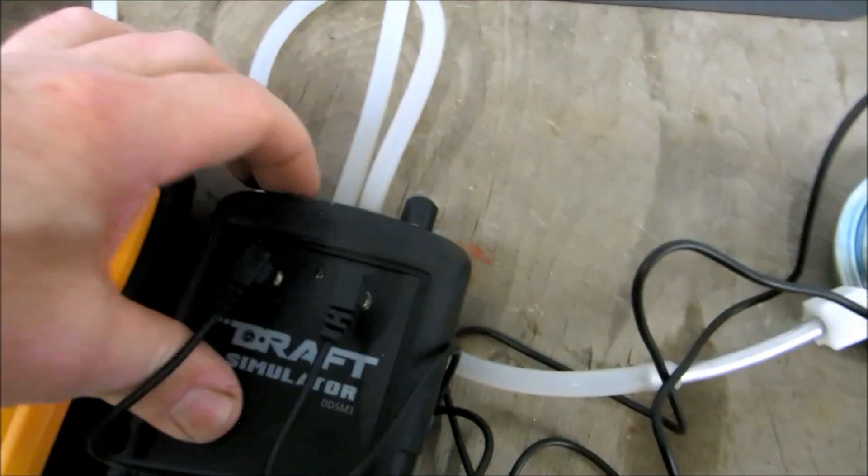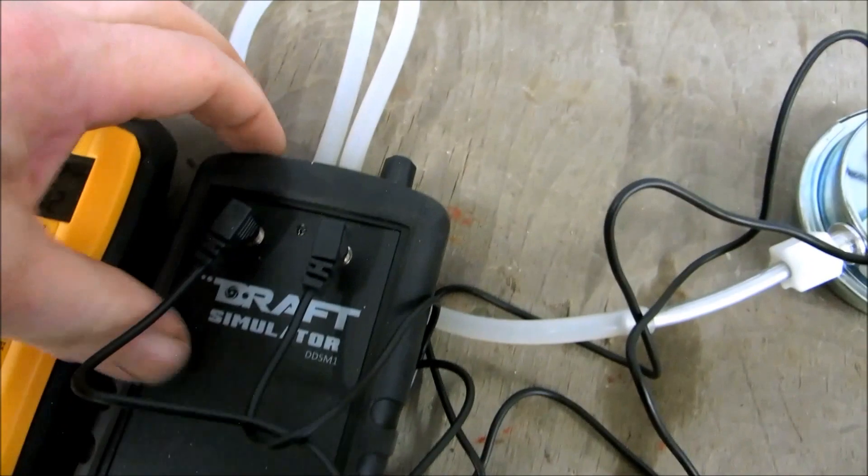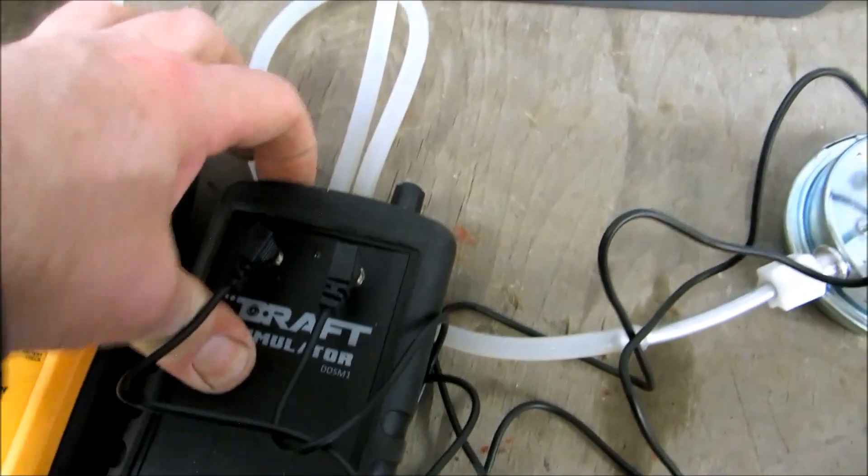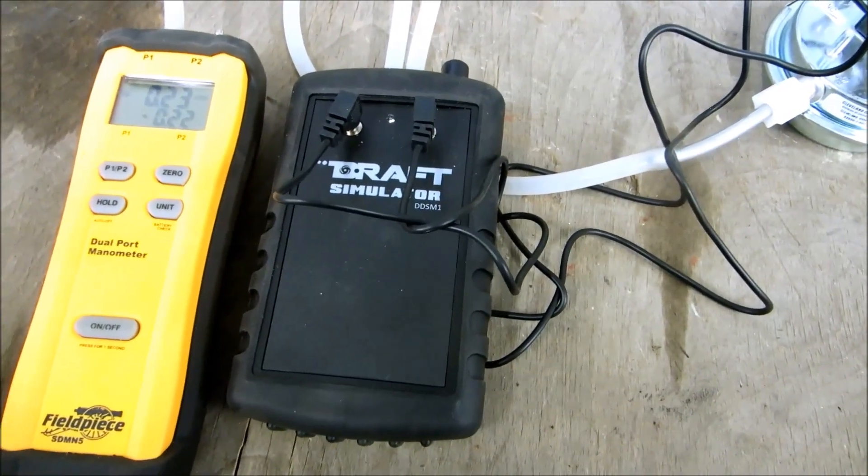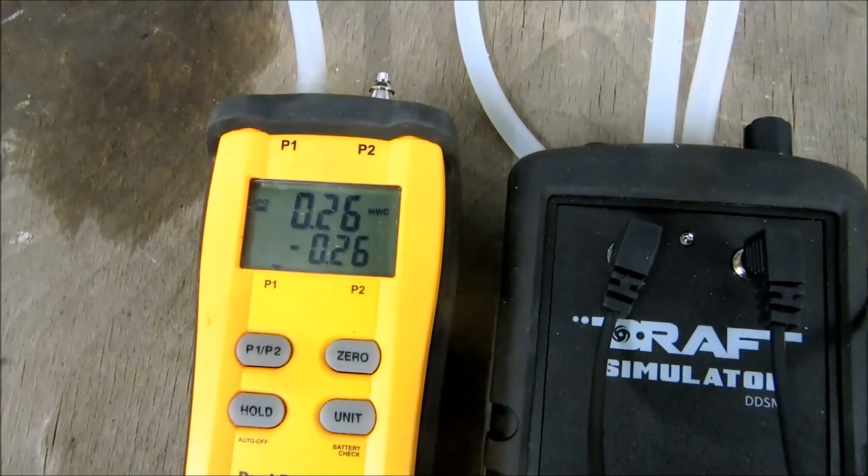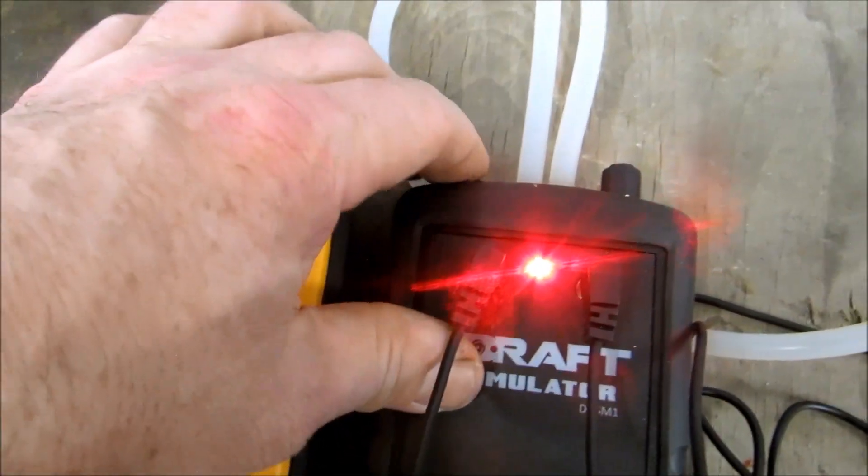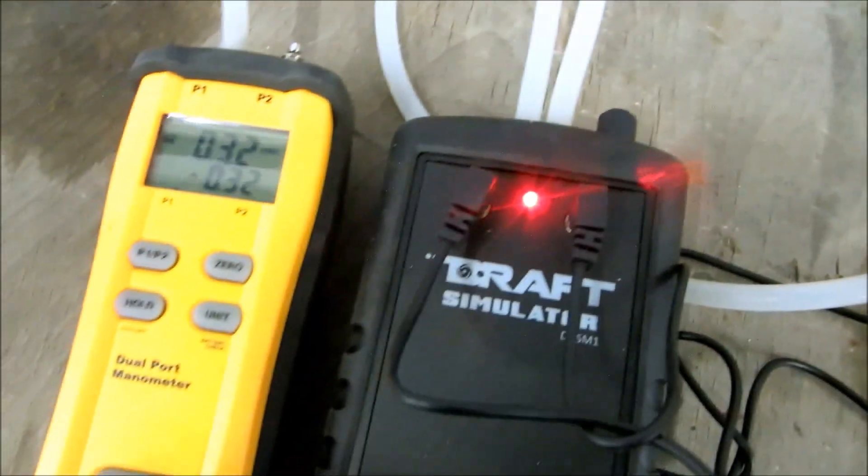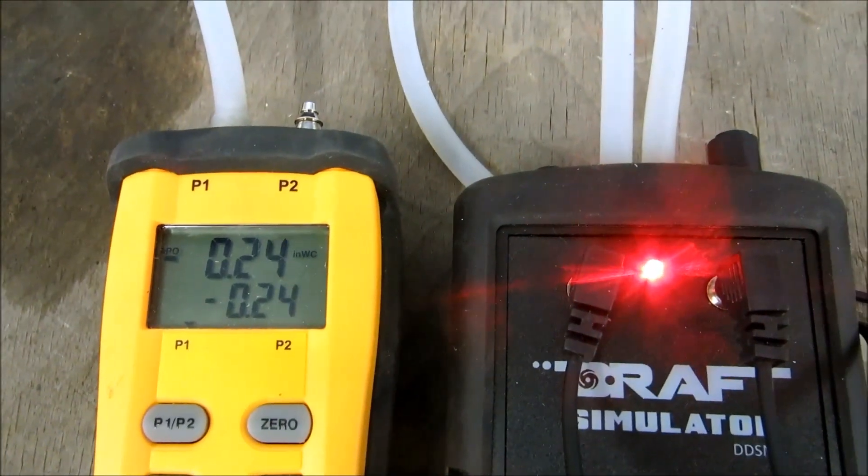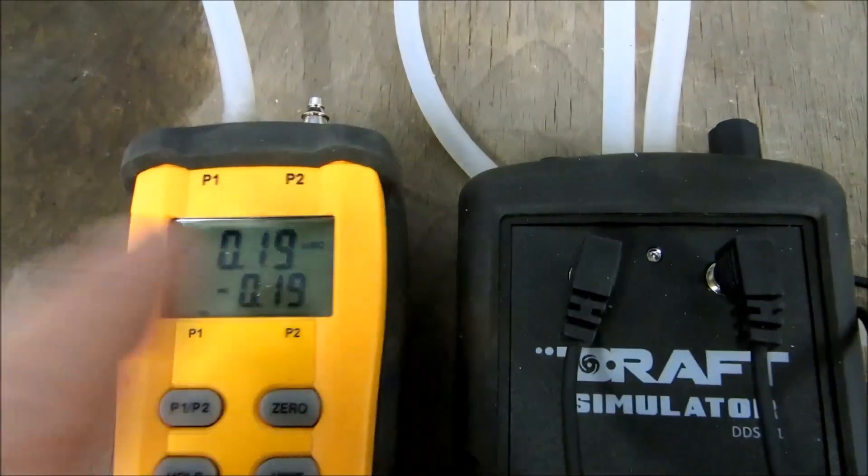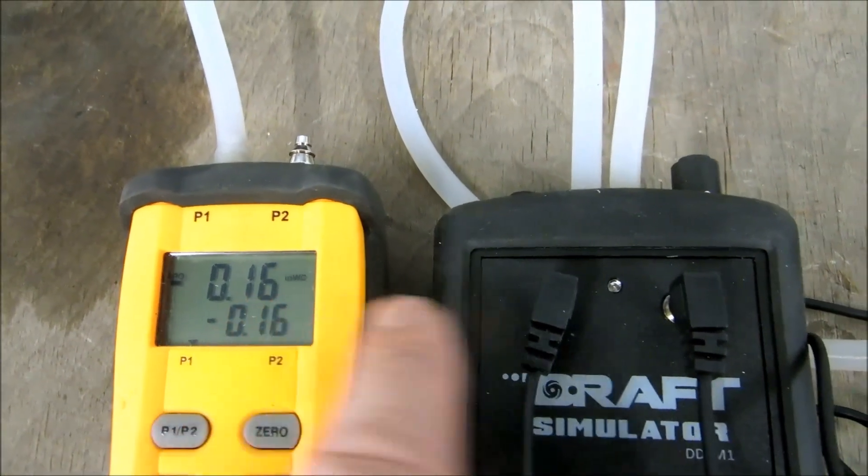And that's another way you can do it, is just shut it off and wait for it to... 2.8, okay? I'm at 3.2 and I'm gonna shut it off. I'm gonna wait for it to drop. Okay, and it kicked in at 2.1.